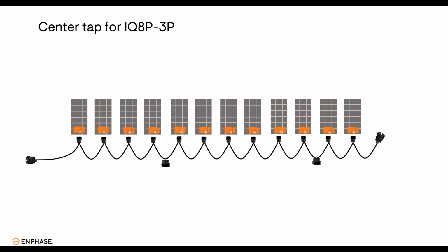If we're starting from drop 3, the center tap plugs will fall between 4 and 5, and between 10 and 11. Again, we'd use the one on the left because it's closer to the middle of the circuit and has the most microinverters on either side. A common misconception is that when you hear the term center tap, you think it has to be in the exact center. Really, it just has to be as close to the center as possible. So as long as you pick the center tap connector with the most microinverters on either side, it will work as it should.